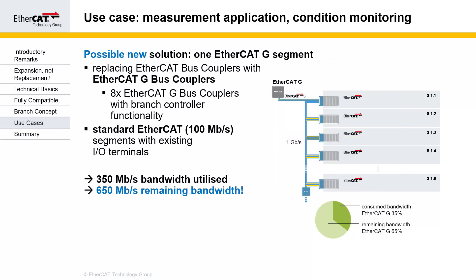If we do the same thing with EtherCAT-G — using an EtherCAT-G backbone with branch controller functionality — we can use the same 100 megabit I/O terminals and the same analog inputs as before, but send the data over the gigabit backbone much faster. Instead of more than 80% bandwidth utilization, we only utilize about a third of the bandwidth, leaving a lot of bandwidth remaining for other data, parameterization, or whatever else we need.